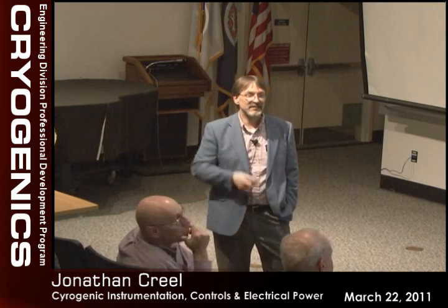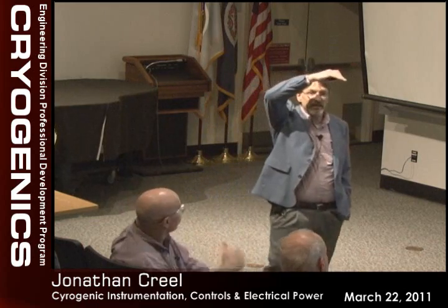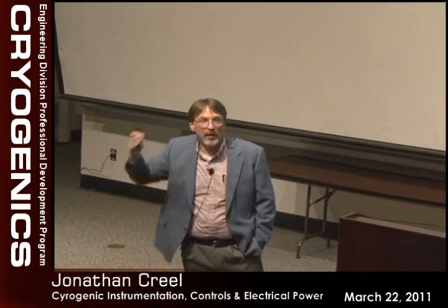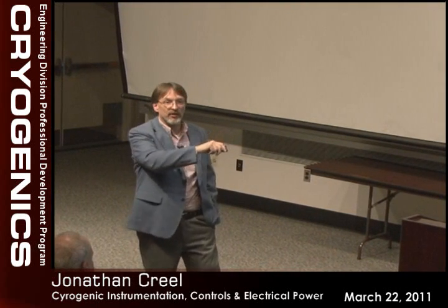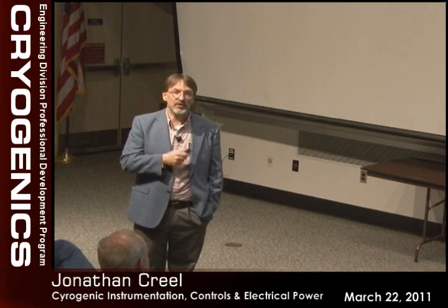So Jonathan, is it that you have to be careful with your insulation mainly because the wires in a vacuum get so much hotter? Yeah, inside of a vacuum, any wires that are carrying a significant amount of current will heat up. And you have to plan your routing through the cold box, and you have to plan your insulation to take that into account. And like I said, it comes into play on our systems because we have beds inside of a cold box which have big heaters on them. And so you got to plan that.